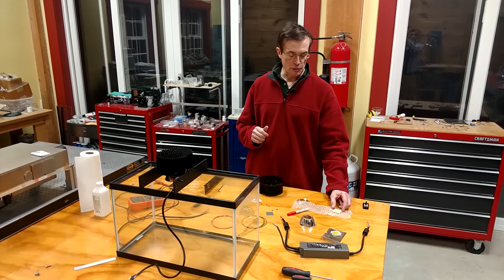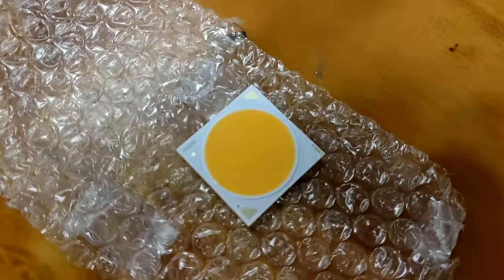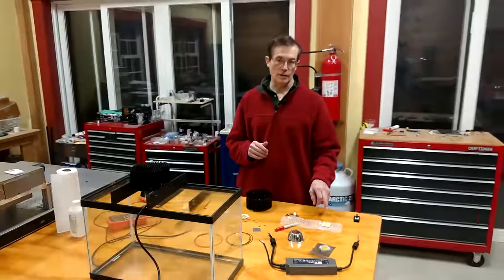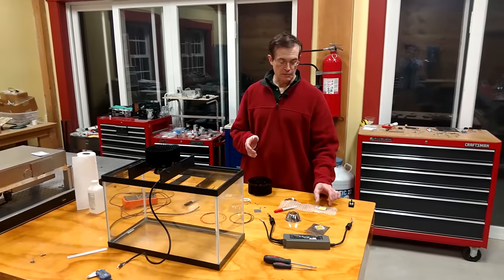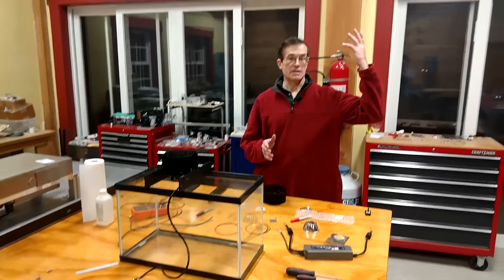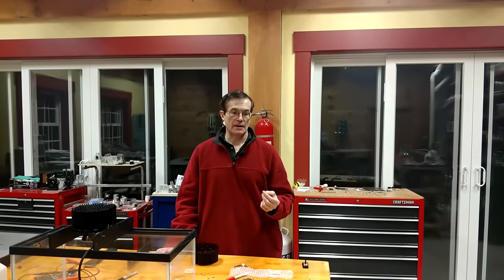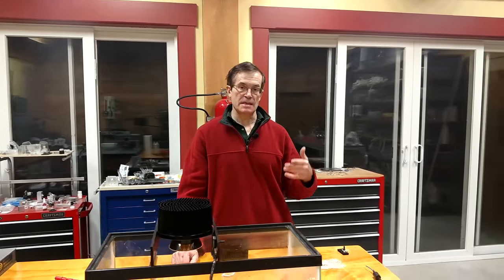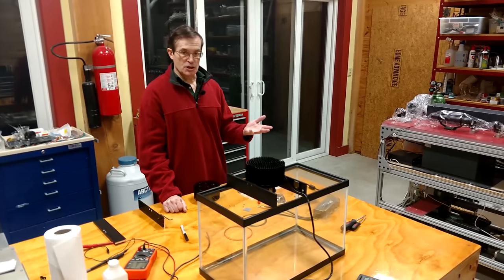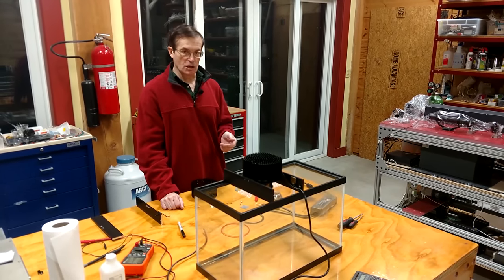This particular unit from Cree — one of the world's best manufacturers, with Philips as another good competitor — will handle up to 100 watts of input. Because it's so efficient at 140 lumens per watt, this module will make over 14,000 lumens — as much light as one of the fixtures in this room. It's about 40% more efficient than the next most efficient source, the high-output T5 fluorescent, and more efficient than HID or any other fluorescent lighting.